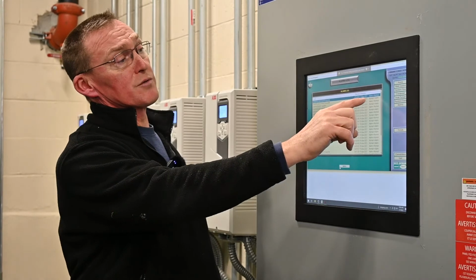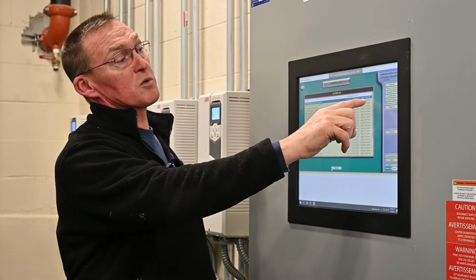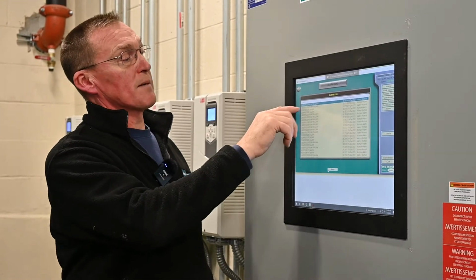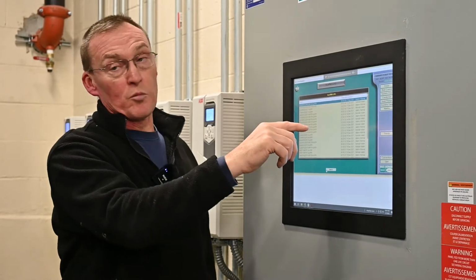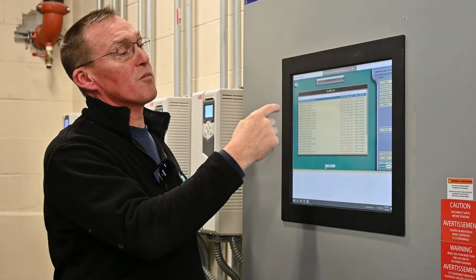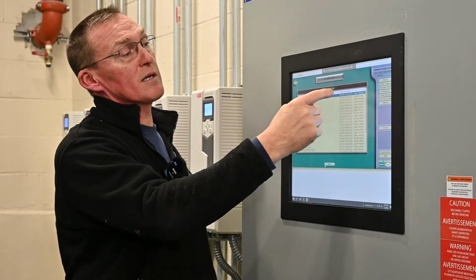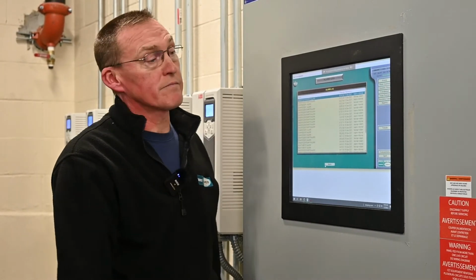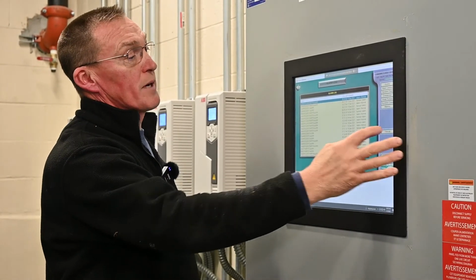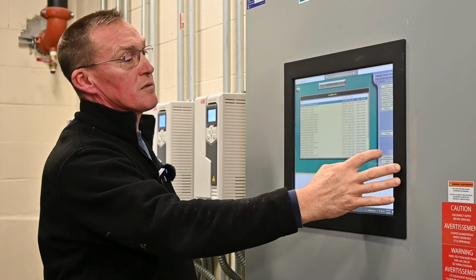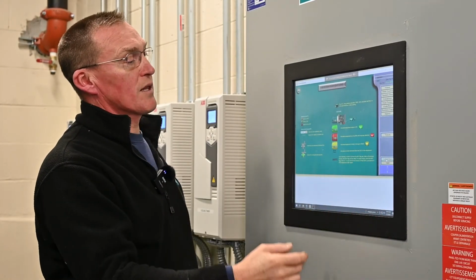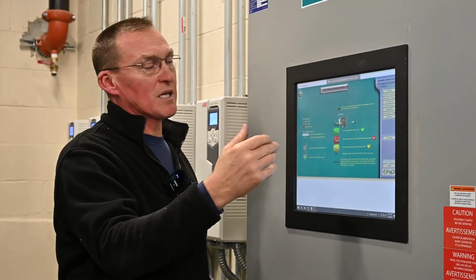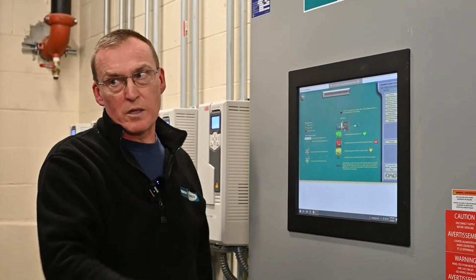As you'll note, it says alarm to normal, normal to alarm. So if something comes in, it's going to go normal to alarm state, and then when it is fixed, it goes from alarm to normal state. Okay? Trends I'll go over out there because it's easier. Conventions is nothing more than just showing you that if somebody comes in here and turns a pump into hand, it's going to be yellow on the page.